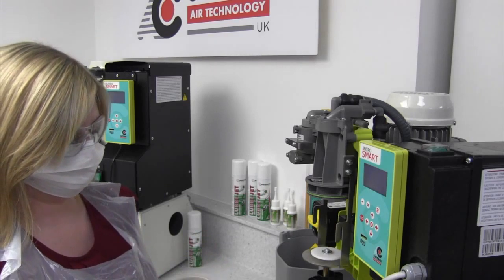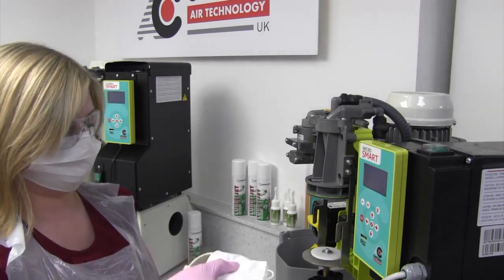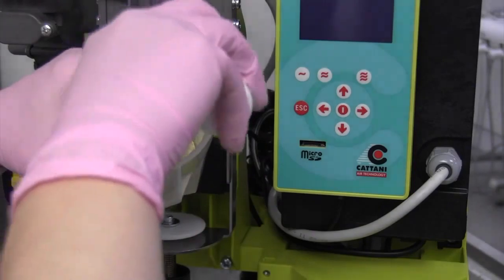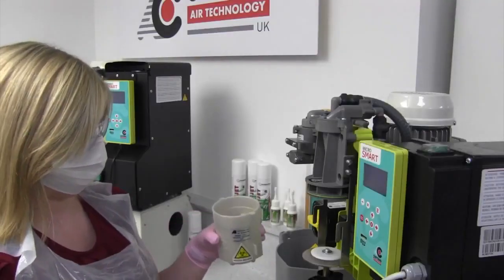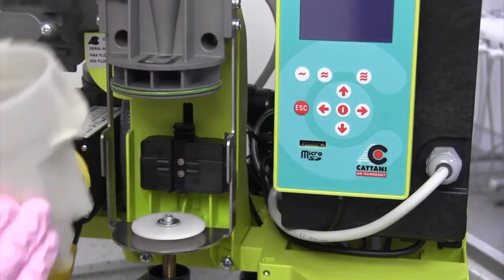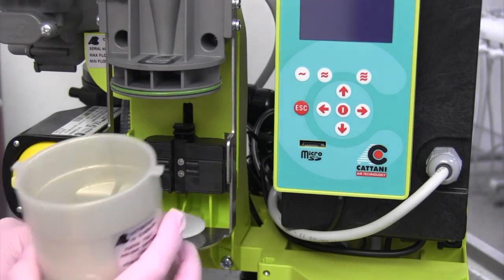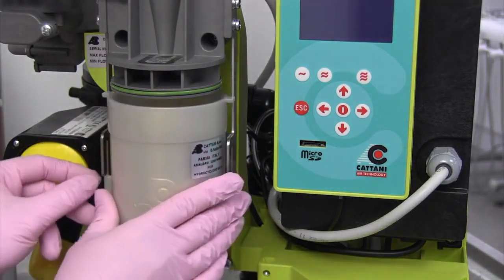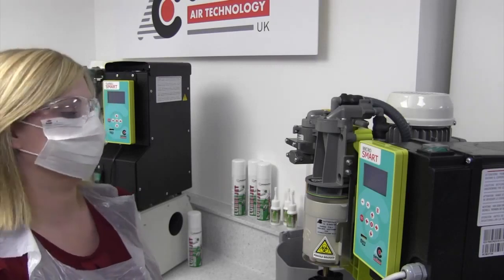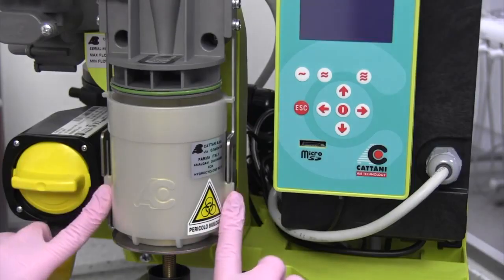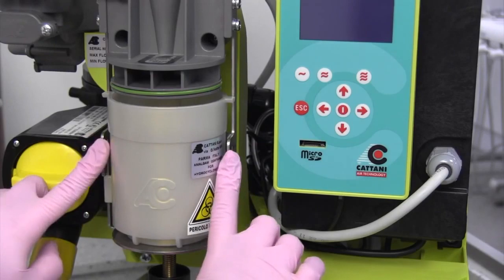Number 4, wipe the inner edge of the amalgam pot and then lubricate the inner edge with a Lubrijet drop or spray. At the base of the amalgam pot is a recess. When replacing the pot, you must ensure that the disc sits within the recess. Number 6. Also ensure that the plastic lugs on either side of the pot locate correctly into the retainer.